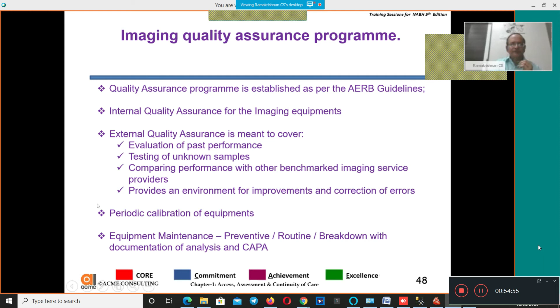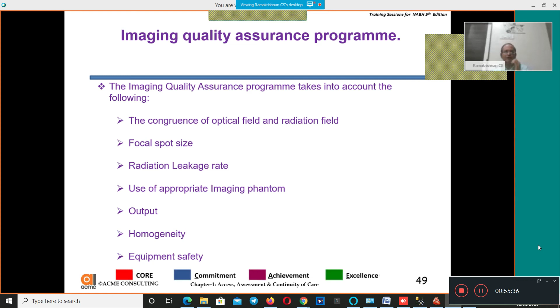Then, when we talk about the quality program for the imaging equipment, these are the factors which are normally required. One is the congruence of the optical field and radiation field. You have to be congruent. Otherwise, you will have errors. Focal spot size is another requirement. Radiation leakage could also affect the performance of the imaging output. Use of appropriate imaging phantom to verify your image clarity. Output related requirements, homogeneity, equipment safety. So these are the things which the imaging personnel know what is to be done. So all these are brought into the conversation.